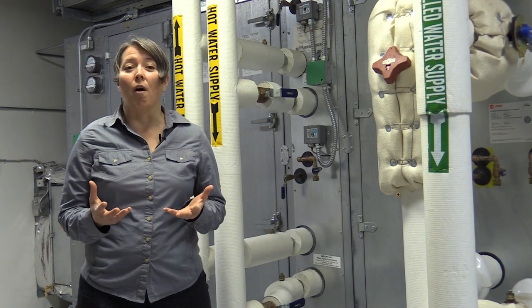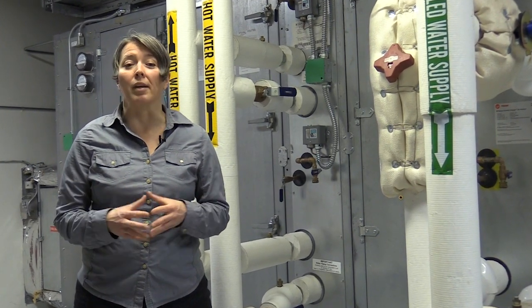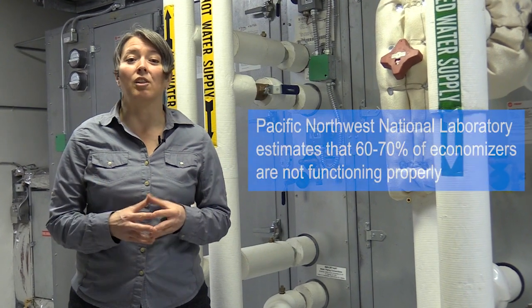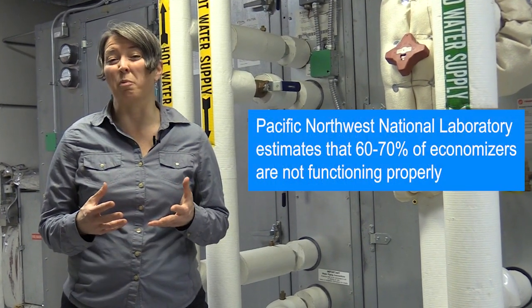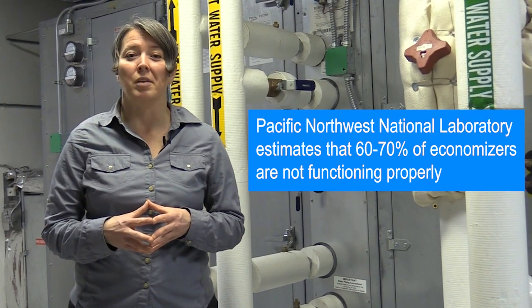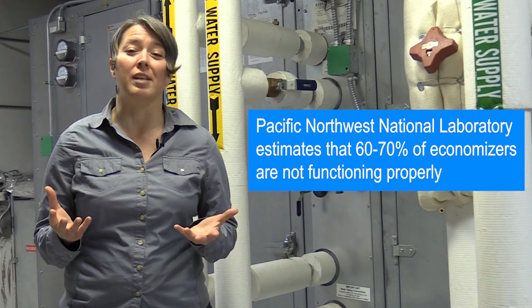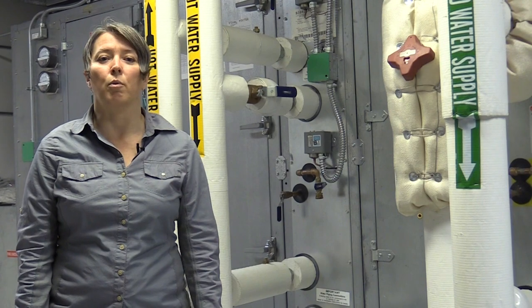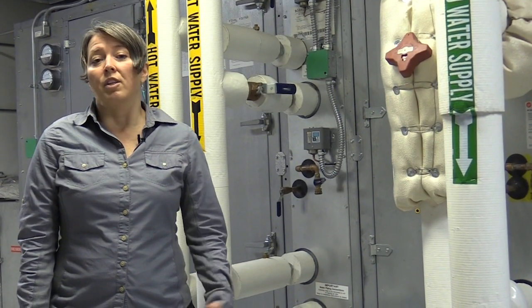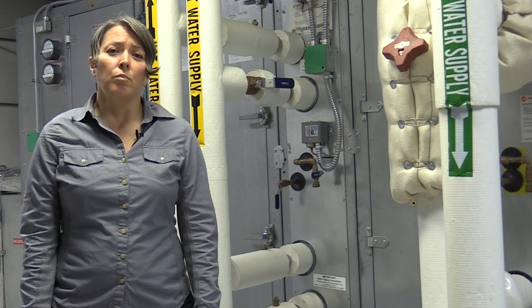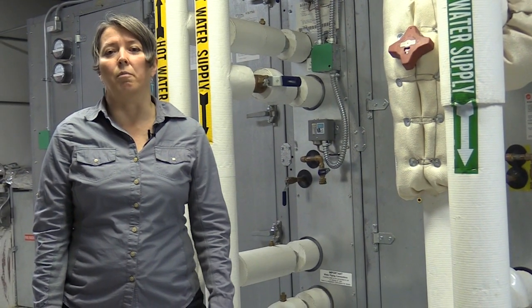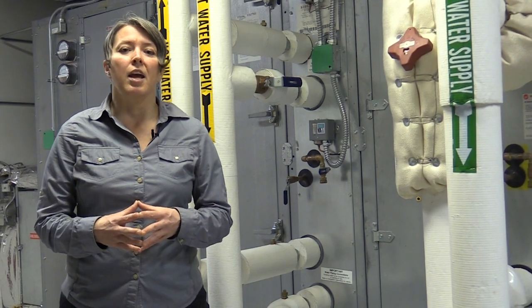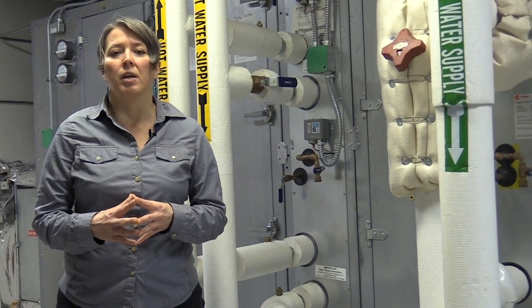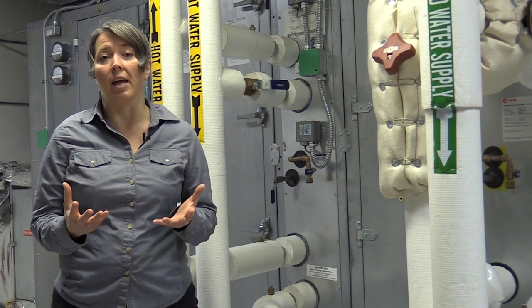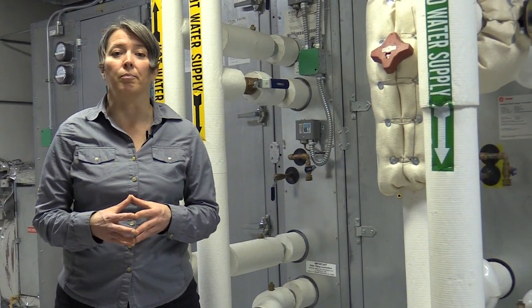Unfortunately, economizers are often not working properly, and the Pacific Northwest National Labs, in fact, estimates that about 60 to 70% of economizers are not functioning properly. So this is a big opportunity for savings that is often missed. And economizer control happens a couple of different ways. Often in packaged rooftop units and air handlers, the control happens via the integrated controllers for the unit, and so remote monitoring is not an option. And this is where data loggers can be really handy in verifying that the control strategy is working properly.